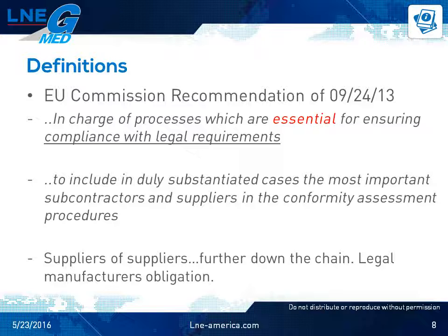We move on to a second take on critical suppliers, that of the EU Commission in its recommendation of September of 2013. The trend in definition is becoming clear. Those suppliers that are in charge of activities critical to the conformity of the device will be the focus in conformity assessments. The verification of compliance by notified bodies includes performing the regular and unannounced audits for the legal manufacturer and, when required, the critical suppliers or subcontractors.